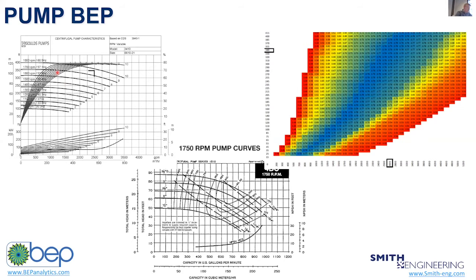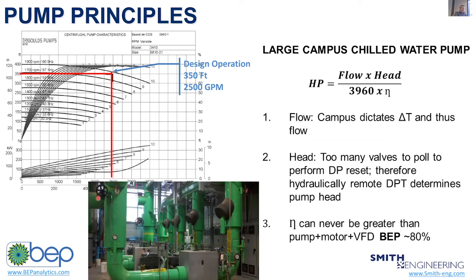So my first example is pump staging. This is a problem that is solved pretty easily from a keep-it-running perspective, but in very rare cases is it done optimally. So I have some examples of pump curves here for Princeton. On the thermal storage plant, they have 400 horsepower chilled water distribution pumps. The pumps are oversized on head, which is typically what's done because you want to be able to plan for future growth of the campus. And you also are nervous because you calculated head and you don't want to install a pump that doesn't have enough. So you always kind of oversize it as a consulting engineer.